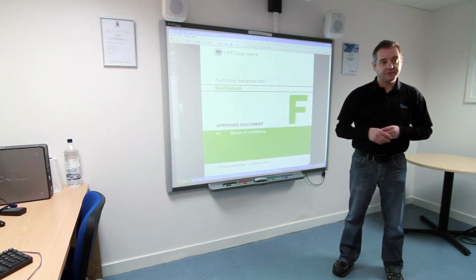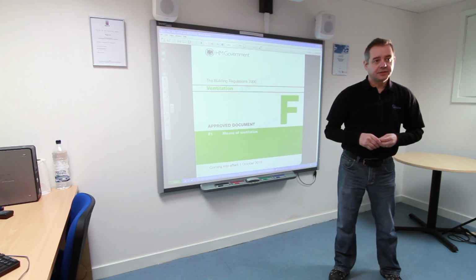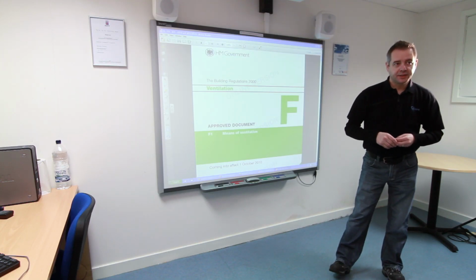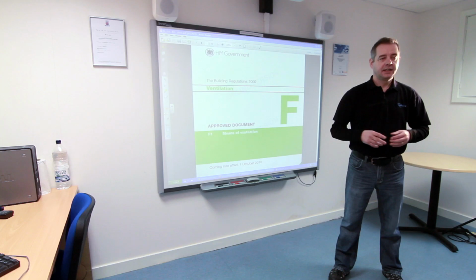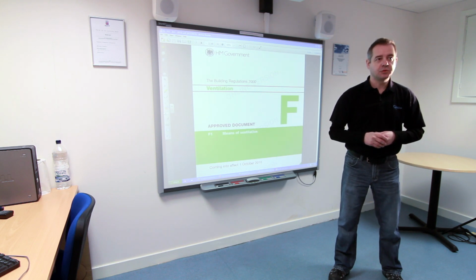In October 2010, the building regulations, Part F in particular, changed quite dramatically, whereas ventilation is now more of a controlled service. Part F of the building regulations is the means of ventilation within a property, and one of the key changes in the 2010 building regs was the need to commission every ventilation system that's installed. Later on in the video, we'll be showing you exactly the process you need to go through and the instrumentation needed to comply with the building regs and commission a system.